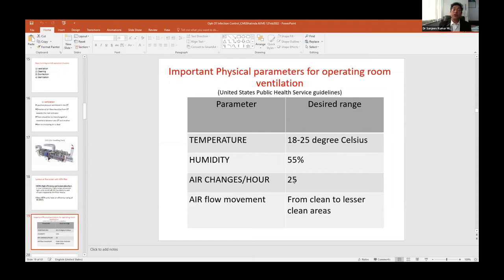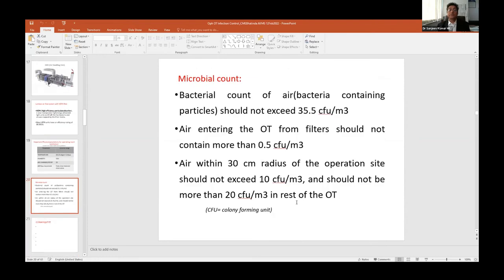There are certain important physical parameters for operation room ventilation. The temperature should range between 18 to 25 degrees Celsius, humidity should be around 55%, the air exchange per hour cycle should be around 25, and the airflow movement should be from clean to lesser clean areas.